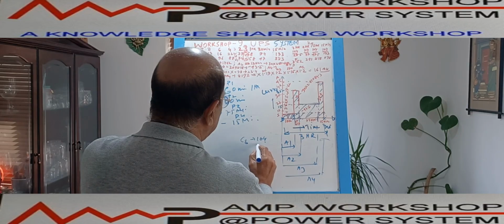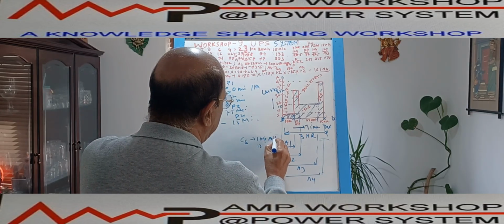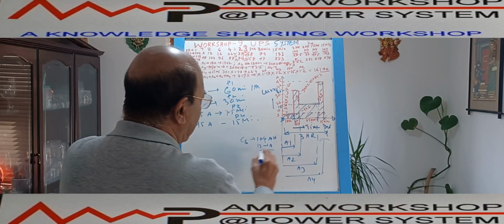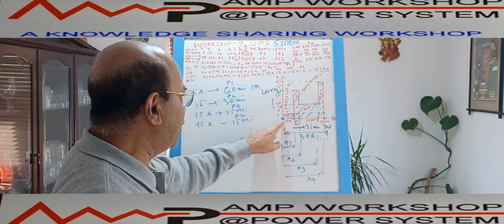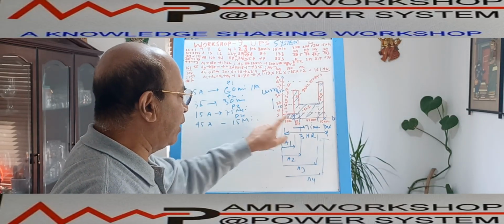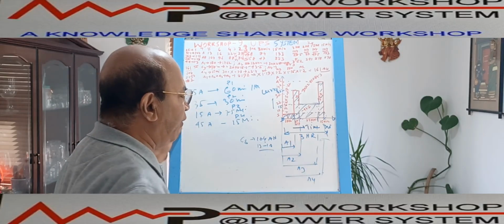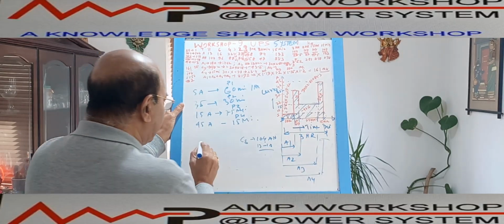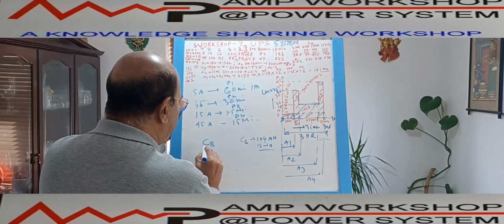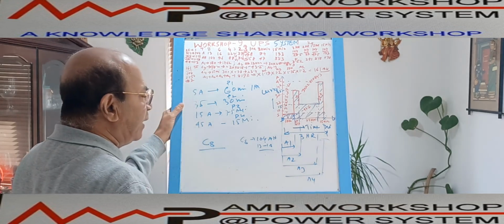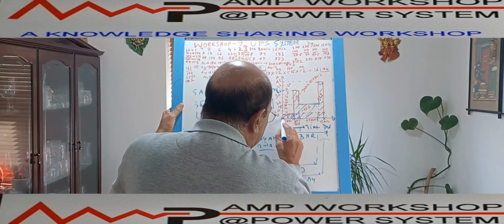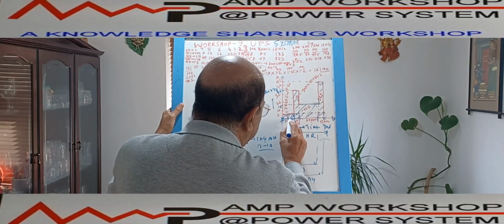That is, a current is 13 ampere. This is ampere hour and this is ampere. Now, for this 5 ampere current, when it is discharging at the rate of 1 hour, what will be the K factor? As per IEEE, it is the battery rated ampere hour divided by the discharge current characteristics of the battery for 1 hour.